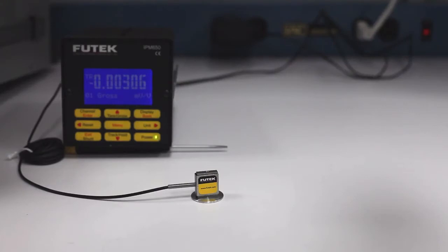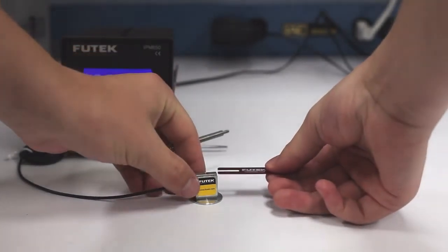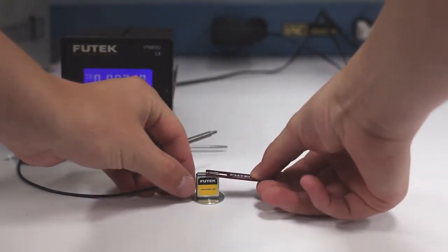Now we will attach a hook to the loading surface of our LSB200. I have already attached a flat loading disc to the bottom surface for added stability. Slide the tool into the sensor so that the loading surface perfectly fills the gap in the tool. There should be no room for the sensor to move.